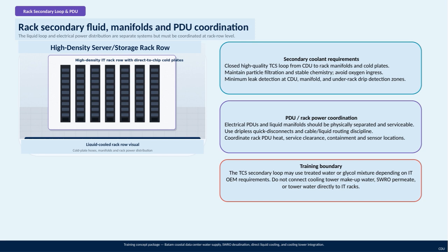Importantly, cooling tower make up water, seawater reverse osmosis permeate, or raw tower water should never be connected directly to the IT racks to protect sensitive equipment. This integrated approach is especially relevant in high-density server and storage rack rows, where efficient cooling and power delivery must be managed flawlessly to support demanding operational needs. The setup here, illustrated by the Batam Coastal Data Center case, includes water supply, SWRO desalination, direct liquid cooling, and cooling tower integration as part of a comprehensive training concept package.